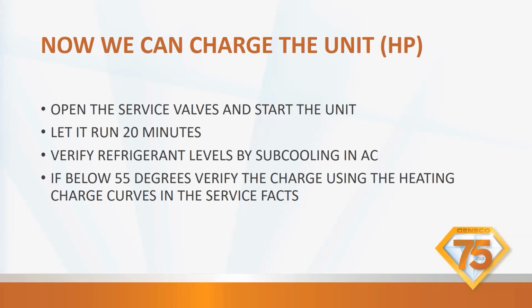I know other brands you can charge down to 17 degrees. So it just depends on where they're willing to make the charts down to, and whether or not they're accurate enough at those lower temperatures. We don't think that they're accurate enough below 55 degrees. That's why we stop at 55. So you're going to verify the charge using the heating charge curves in the service facts. And that's how you're going to set up your heat pump.